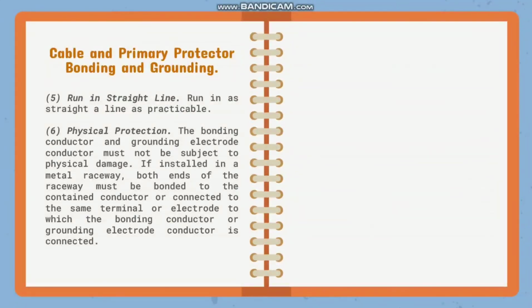And for physical protection, the bonding conductor and grounding electrode conductor must not be subjected to physical damage if installed in a metal raceway. Both ends of the raceway must be bonded to the contained conductor or connected to the same terminal or electrode to which the bonding conductor or grounding electrode conductor is connected. So, yung pag-install po ng ating bonding conductor or grounding electrode conductor sa PVC conduit po is a better practice.